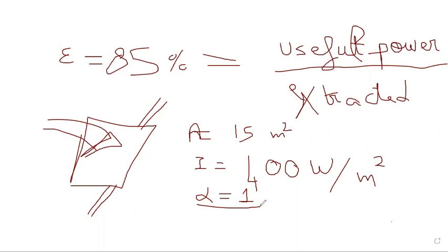In general, for a shower, we should heat water to at least 70 degrees in order to kill bacteria. So T heating should be larger than or equal to 70 degrees. When we do the design, we should make sure that the mass flow rate circulating in the solar panel will provide us this temperature. If not, we should redesign our system in order to reach this temperature.